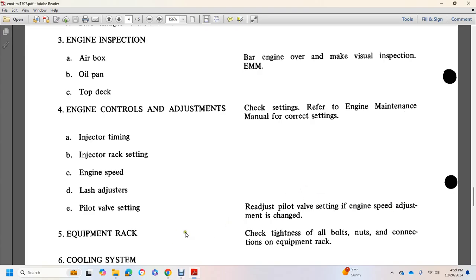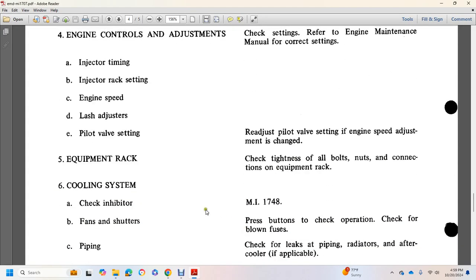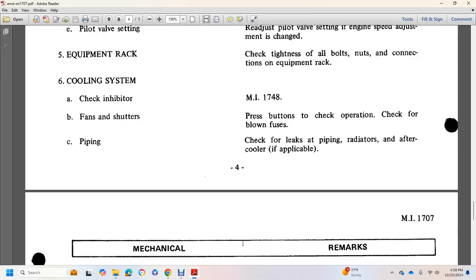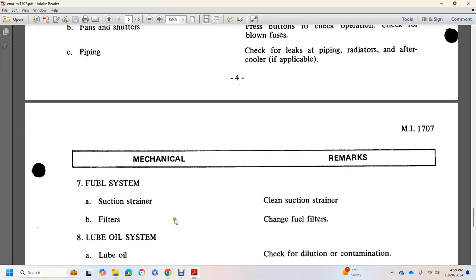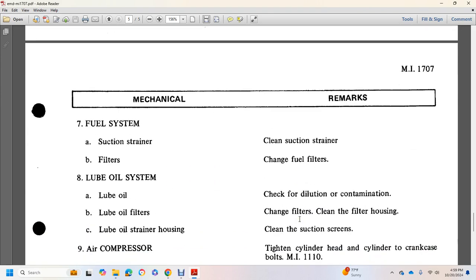Readjust the pilot valve setting if the engine speed adjustment is changed. Equipment rack, check for tightness, all bolts and connections on the equipment rack. Cooling system, check inhibitor, Maintenance Instruction 1748. Fan shutters, press buttons, check operation, check for blown fuses. Piping, check for leaks, piping, radiators, and aftercooler if applicable. Mechanical and remarks. Fuel system, suction strainer, check suction strainer filters, check fuel filters. Lube oil system.